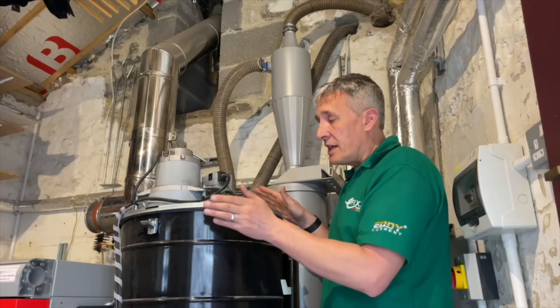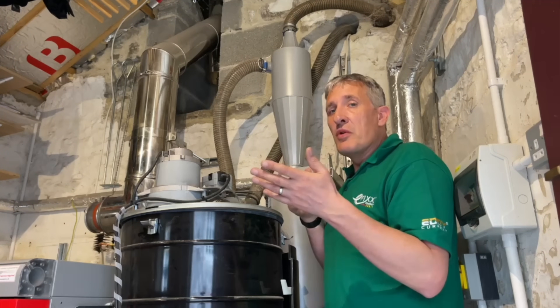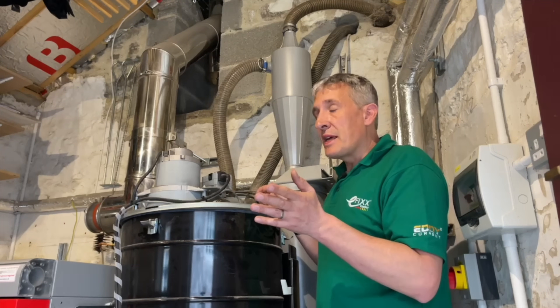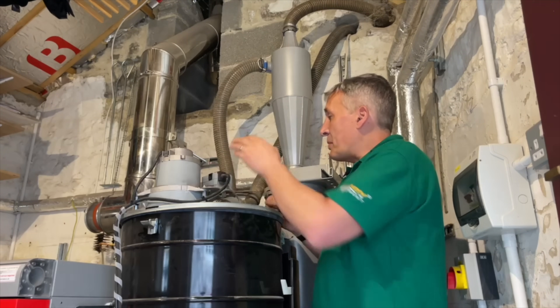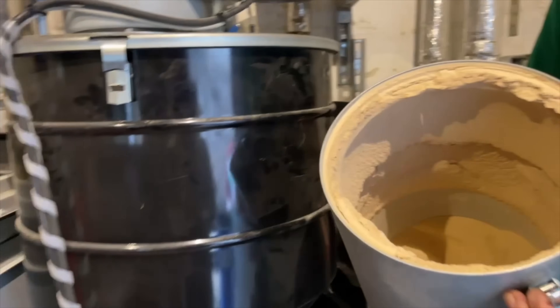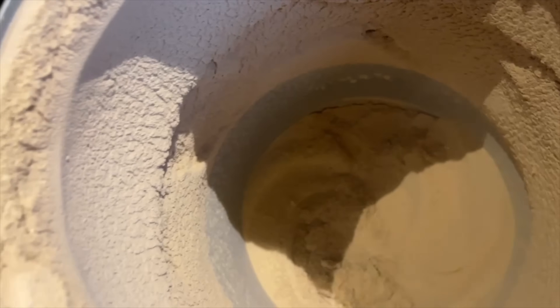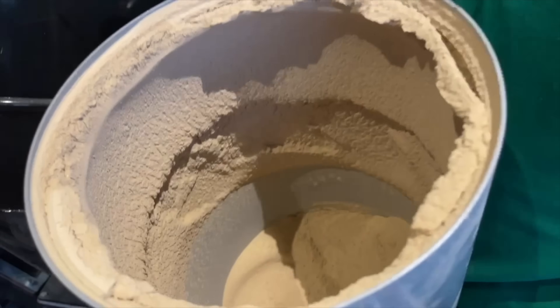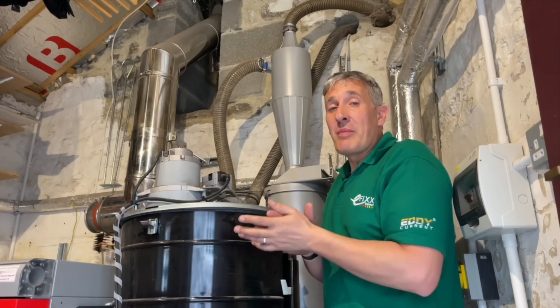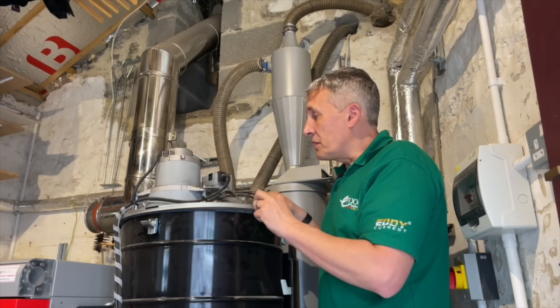The pellets are deposited into this tank, and then there's another clever feature: as pellets move around they disintegrate and dust comes off, so you need to deal with that dust. The waste air goes back up this pipe here through a cyclone — just like you'd see in a Dyson vacuum cleaner — and then back into the store, so we're not drawing any damp air from outside and risking getting the pellets wet.